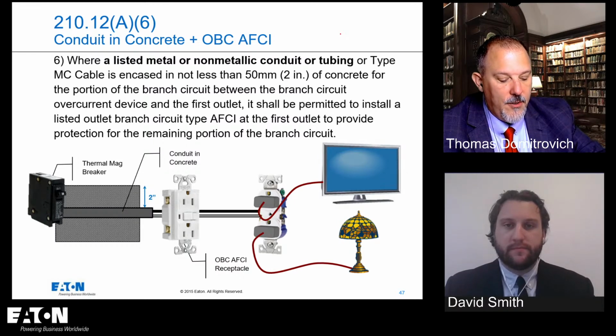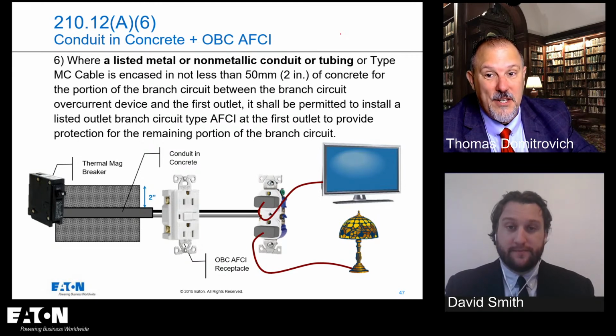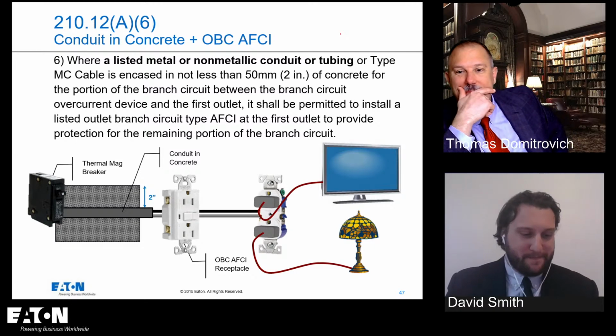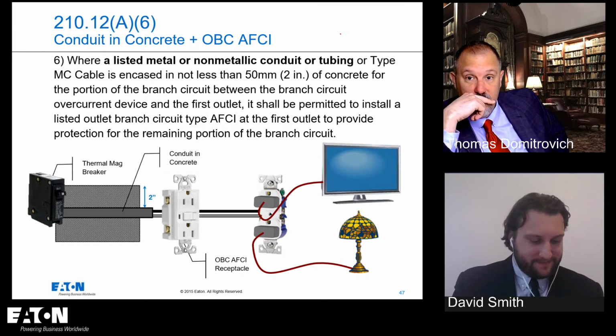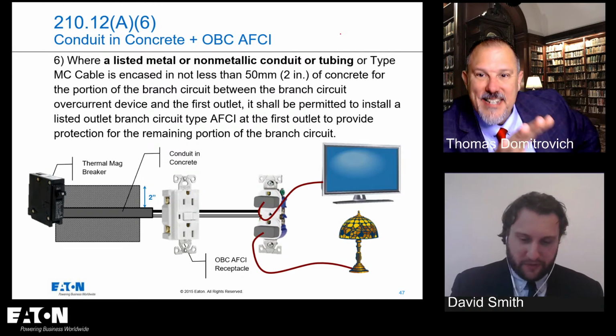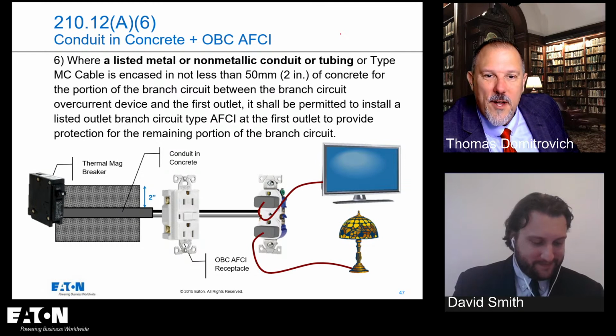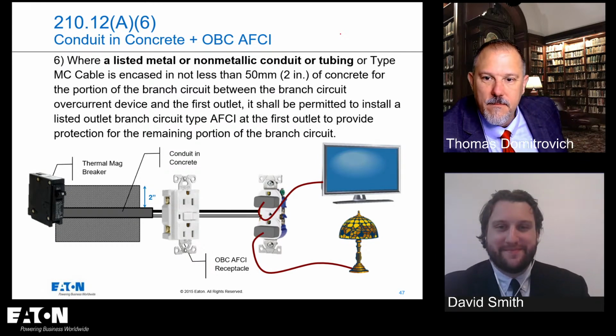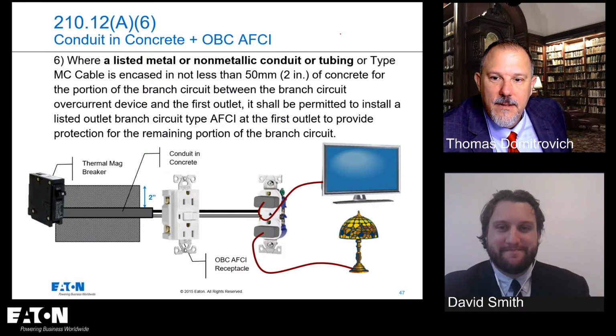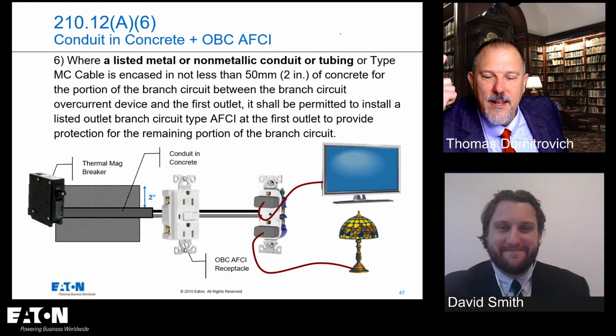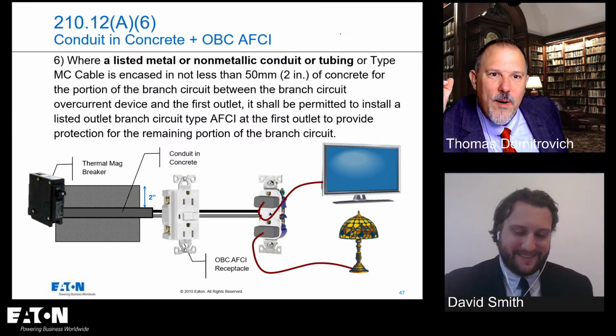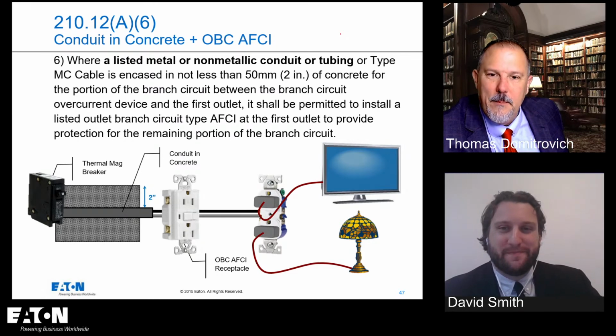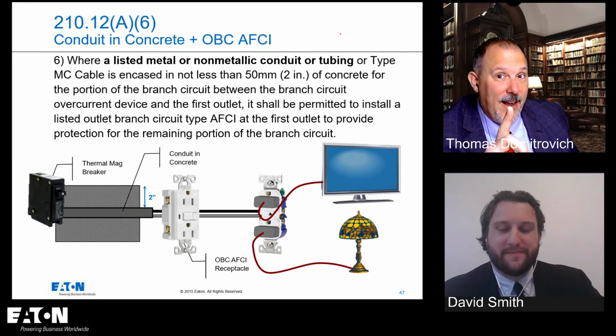And we have now dormitory unit bedrooms, living rooms, hallways, closets, bathrooms, and similar rooms shall be protected. Now, you notice the difference between B and A? We have bathrooms in B, which is interesting because panel 2, one of the rooms that we want to add in A is bathrooms. And we didn't pass it. And I'm scratching my head thinking, wait a second, guys. Whatever arguments that you have for not putting it over there, you've got it in B. Why the heck did you vote for it in B if you're not going to vote for it in dwelling unit? And I don't think it's about safety.